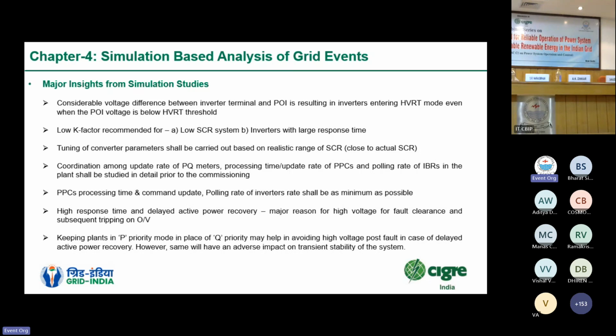And again, there was a difference in the coordination among the update rate of power quality meters, the processing time of power controllers, and the polling rate of IBRs. This issue was also observed in the simulation: different equipment had different processing times and update times, and used different communication protocols and philosophies. All these coordination issues need to be solved so that proper voltage control can be achieved by the simultaneous operation of all these devices. In the power controllers, the polling rate of the inverter shall be as minimum as possible. This was identified because in some cases the inverters were not able to receive the command from the power controllers since their polling rate was very high.